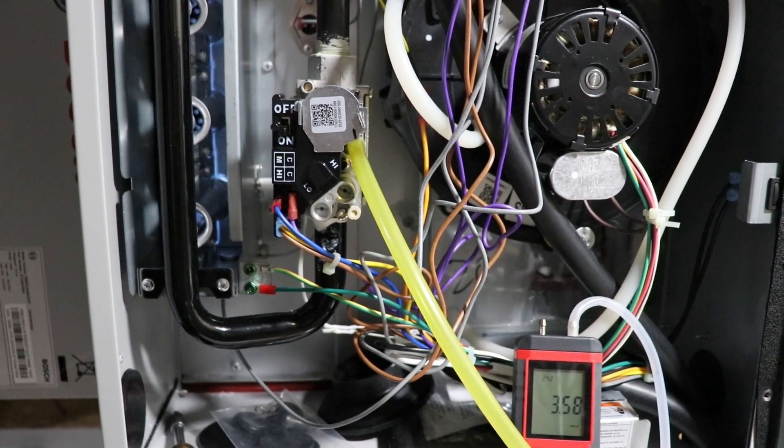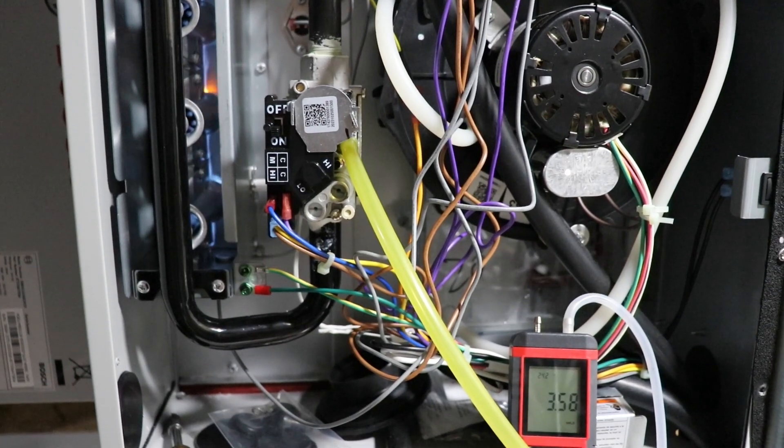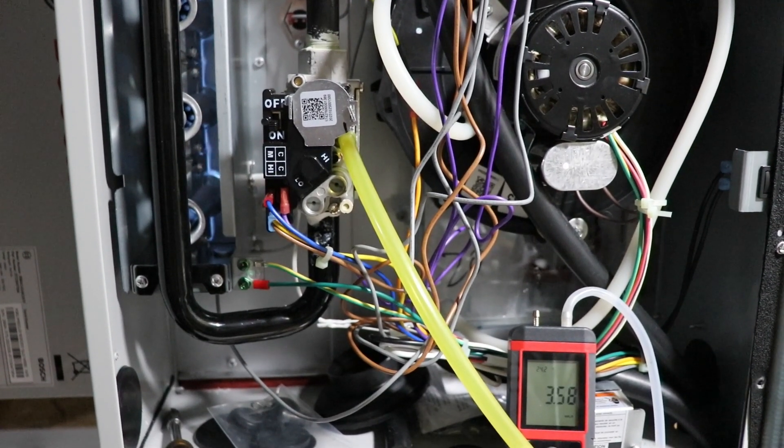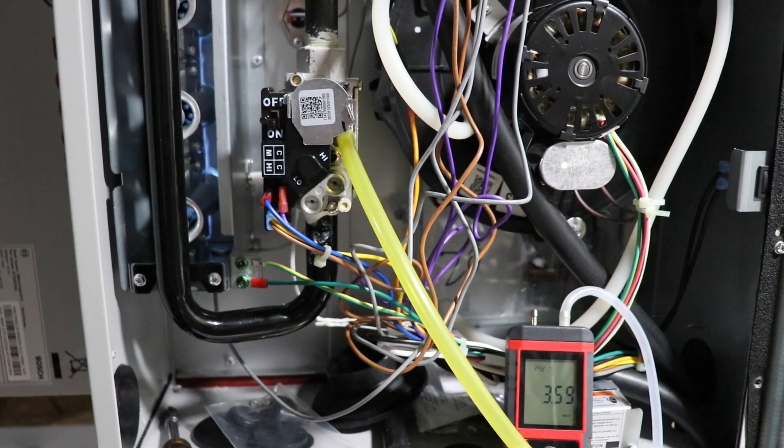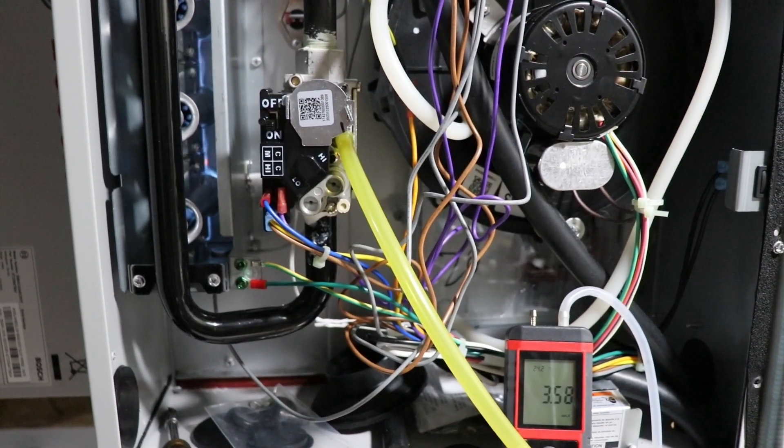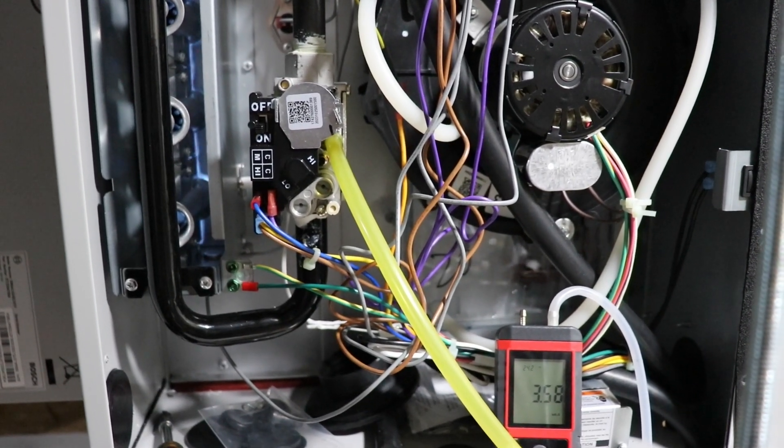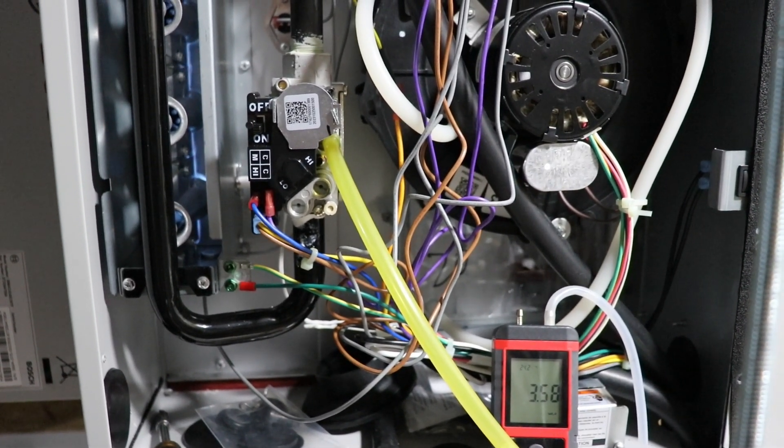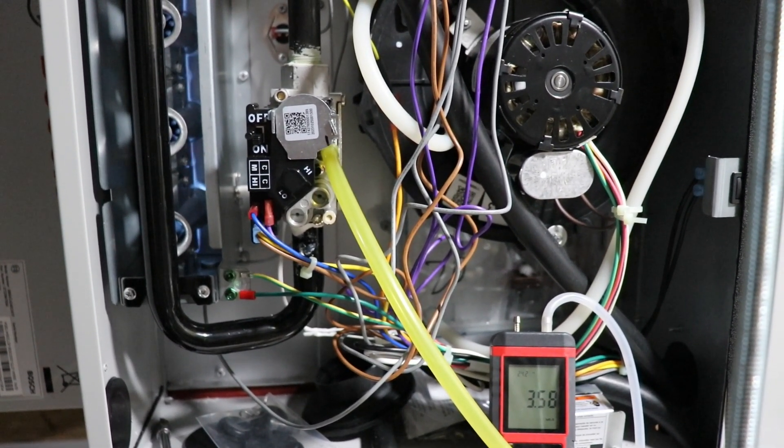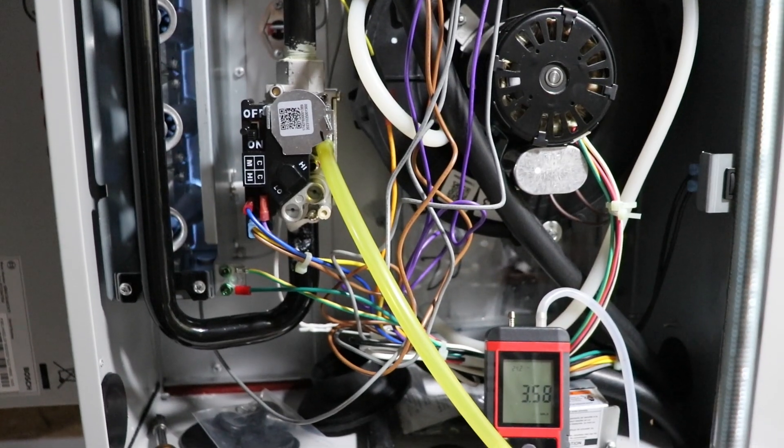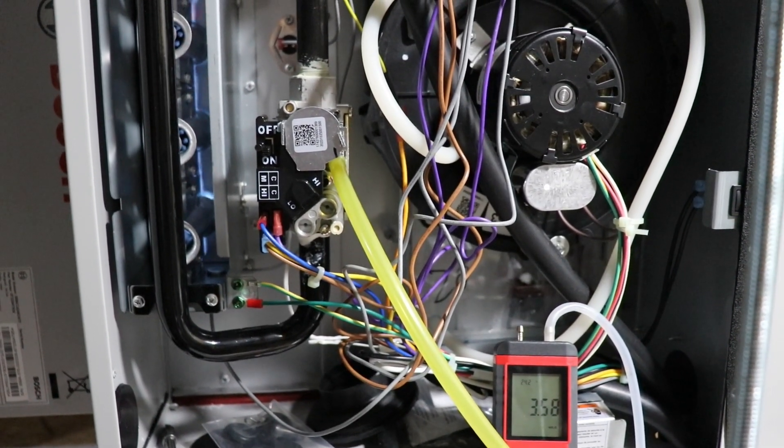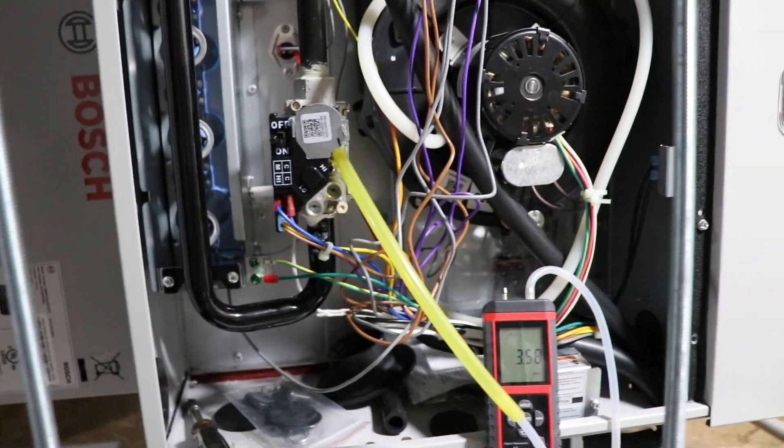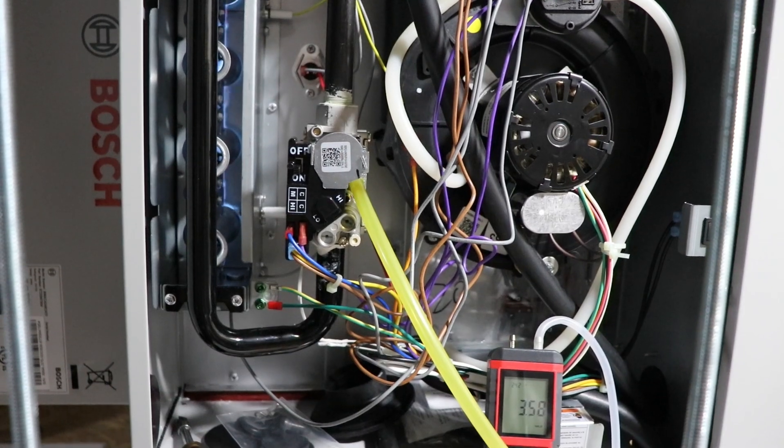Right now, after like perhaps 0.6 degrees or something, it'll move on to the aux heat. But it might take a bit longer than that. You may need to let your temperature drop a little bit before the heat pump really starts working correctly.